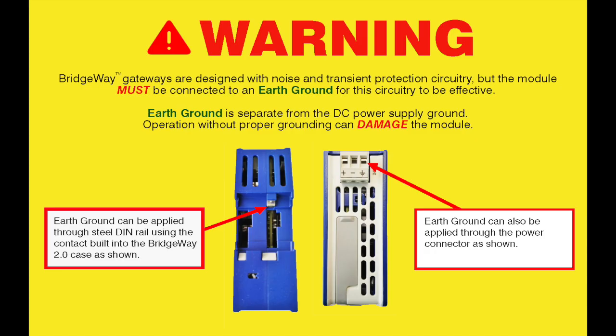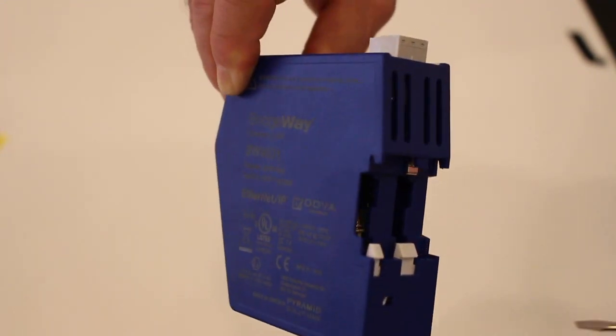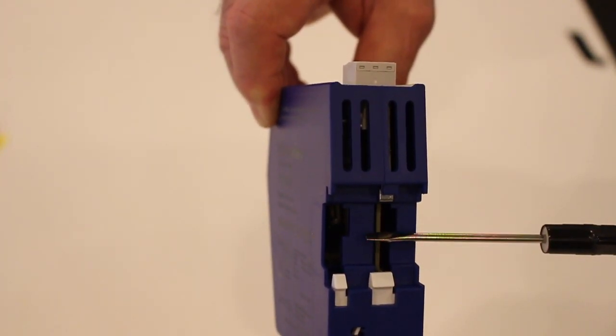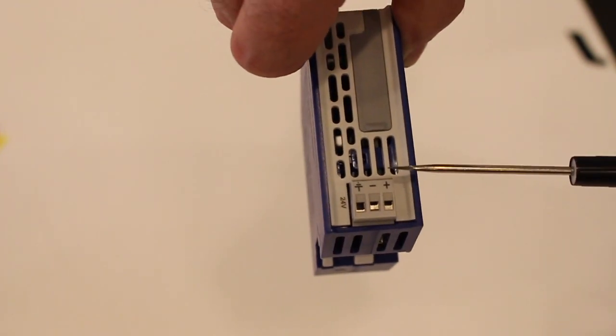Bridgeway 2.0 gateways are designed with noise and transient protection circuitry, but the module must be connected to an earth ground for the circuitry to be effective. Earth ground is separate from the DC power supply ground. Operation without proper grounding can damage the module. Earth ground can be applied through a steel DIN rail using the contact built into the Bridgeway 2.0 case or through the 3-pin terminal block connector.